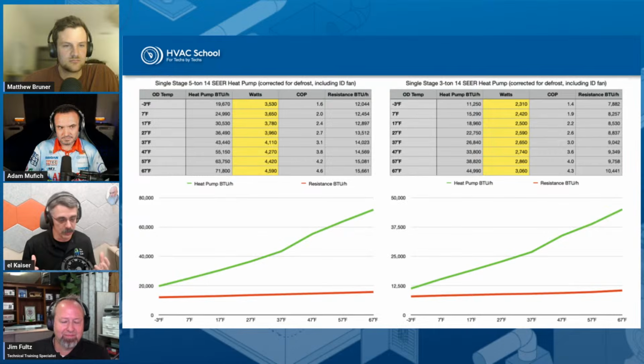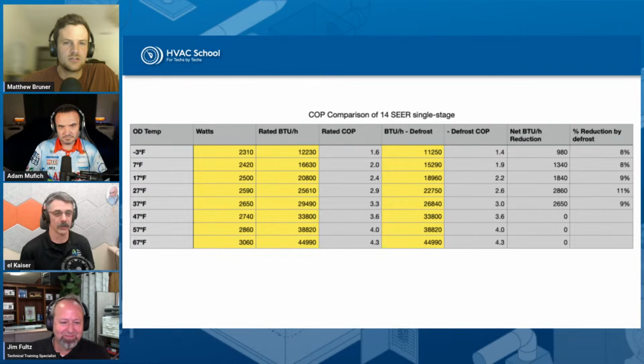Now, why our heat pumps can't pick up as much heat at that point is that we're running into the limits of the vapor compression system and the refrigerants that we use, because we start getting a wider and wider compression ratio as the coil temperatures are farther and farther apart. Yeah. And from my understanding, some of the ways around that are the vapor injection on the variable speed units and things like that. Yeah, there's a lot of different ways to manage that. I'm not necessarily an expert on all of that refrigerant system engineering, so I'm not going to pretend. Okay. Is there anything else you want to hit on this one here?